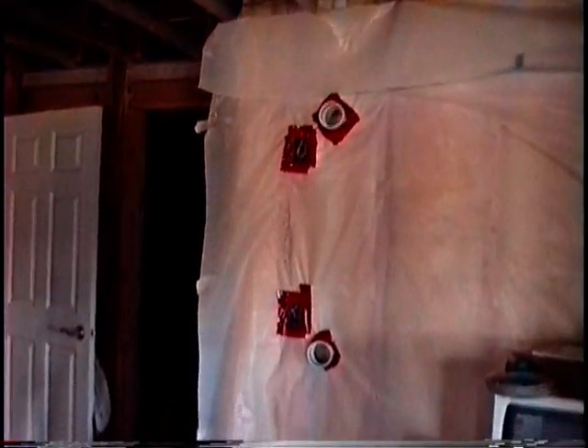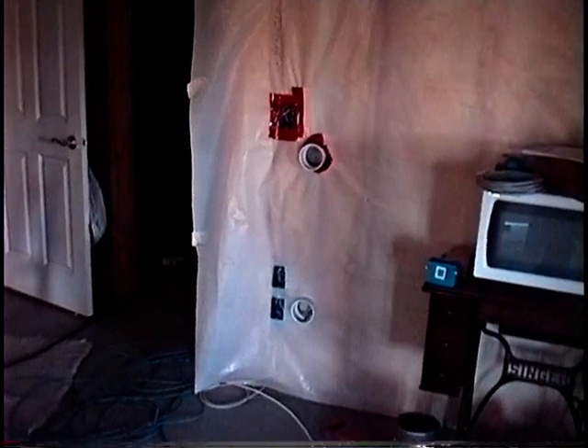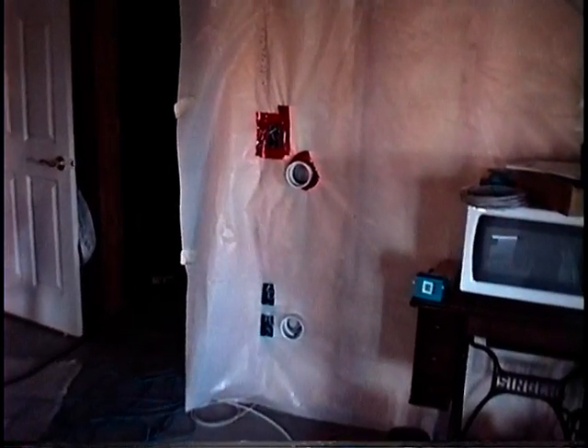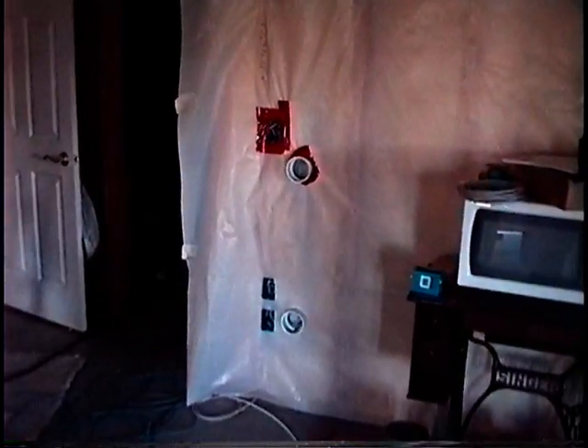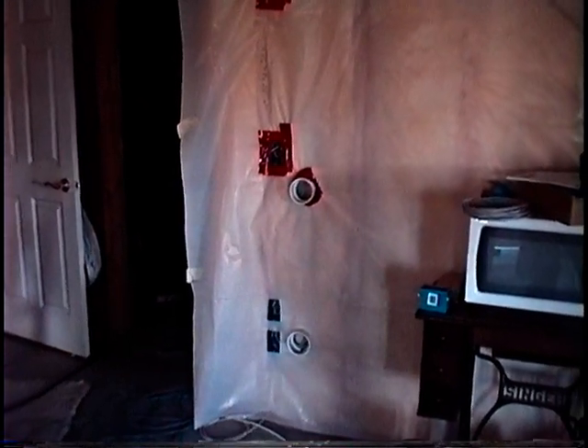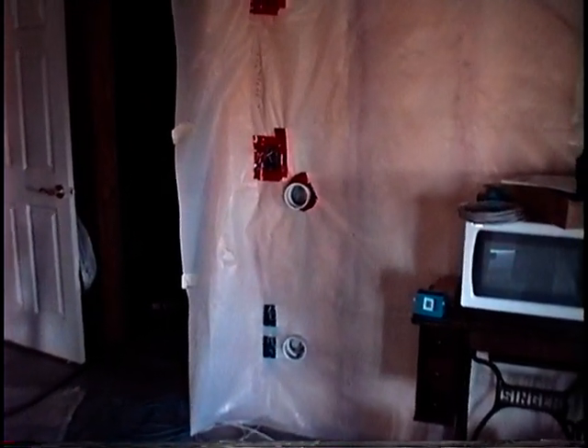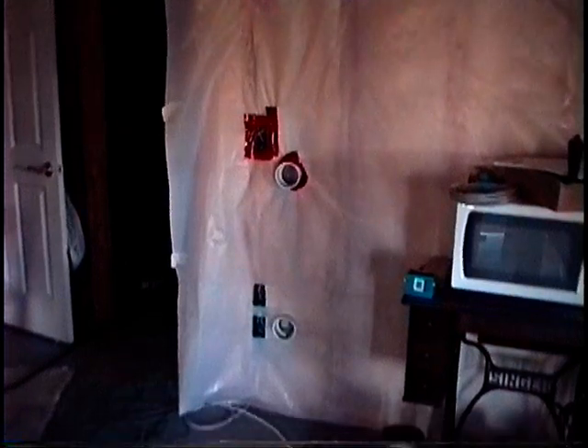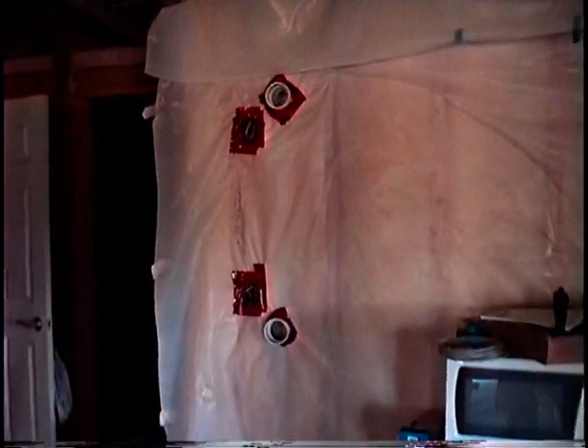There's power outlets from the floor, two outlets with a 12 gauge circuit to each one of the bottom two for 20 amps each, and the second one from the floor also connects to the next two above, which is for more electronics that will be put on the cabinet there.